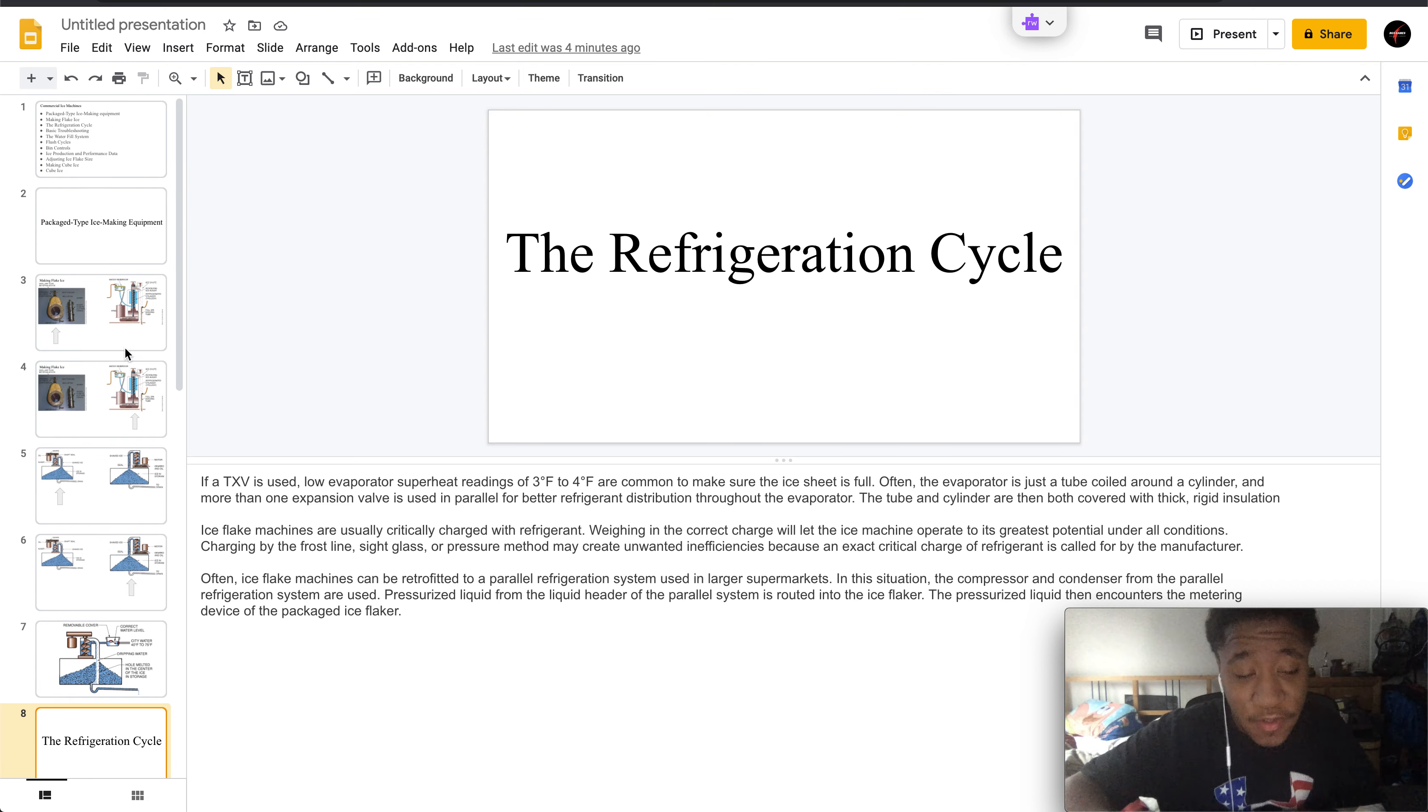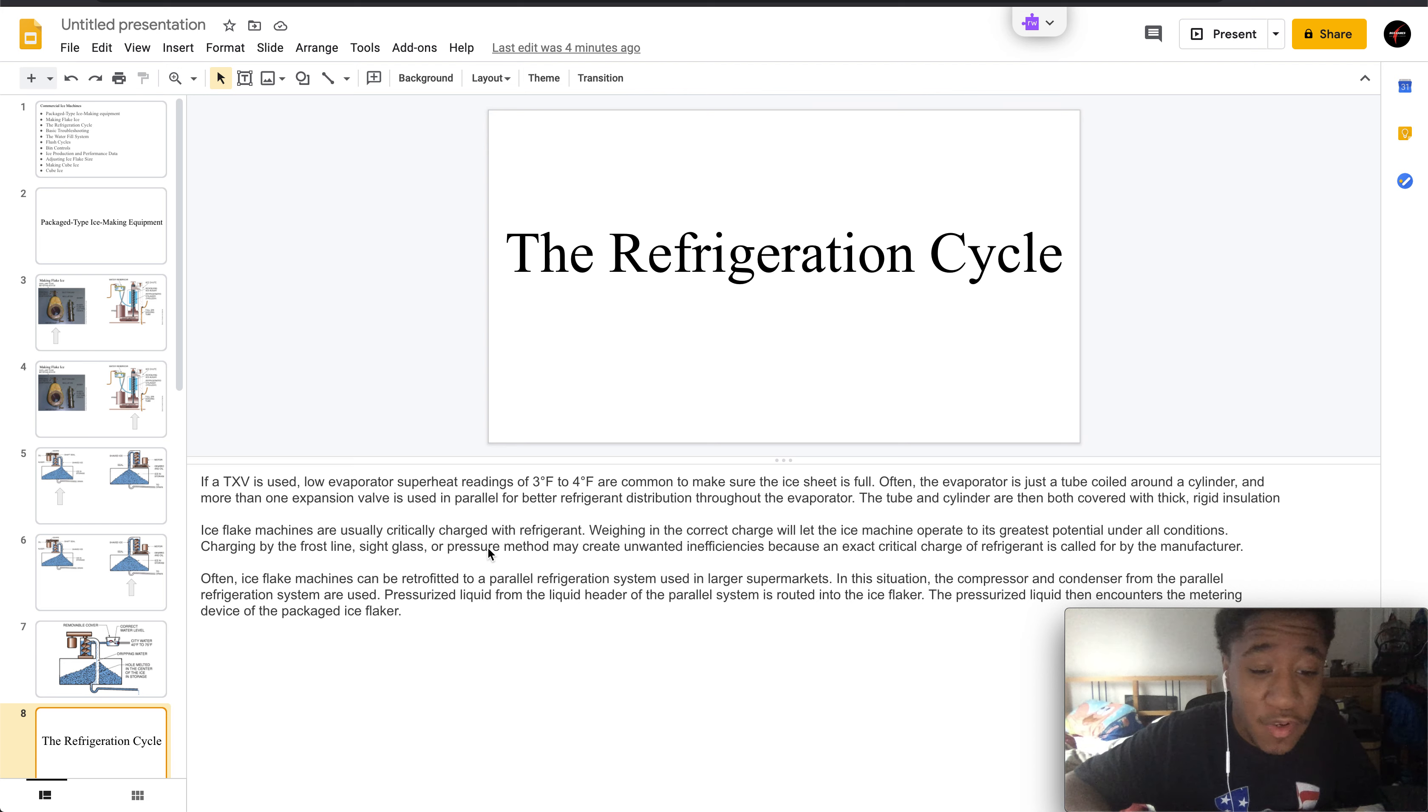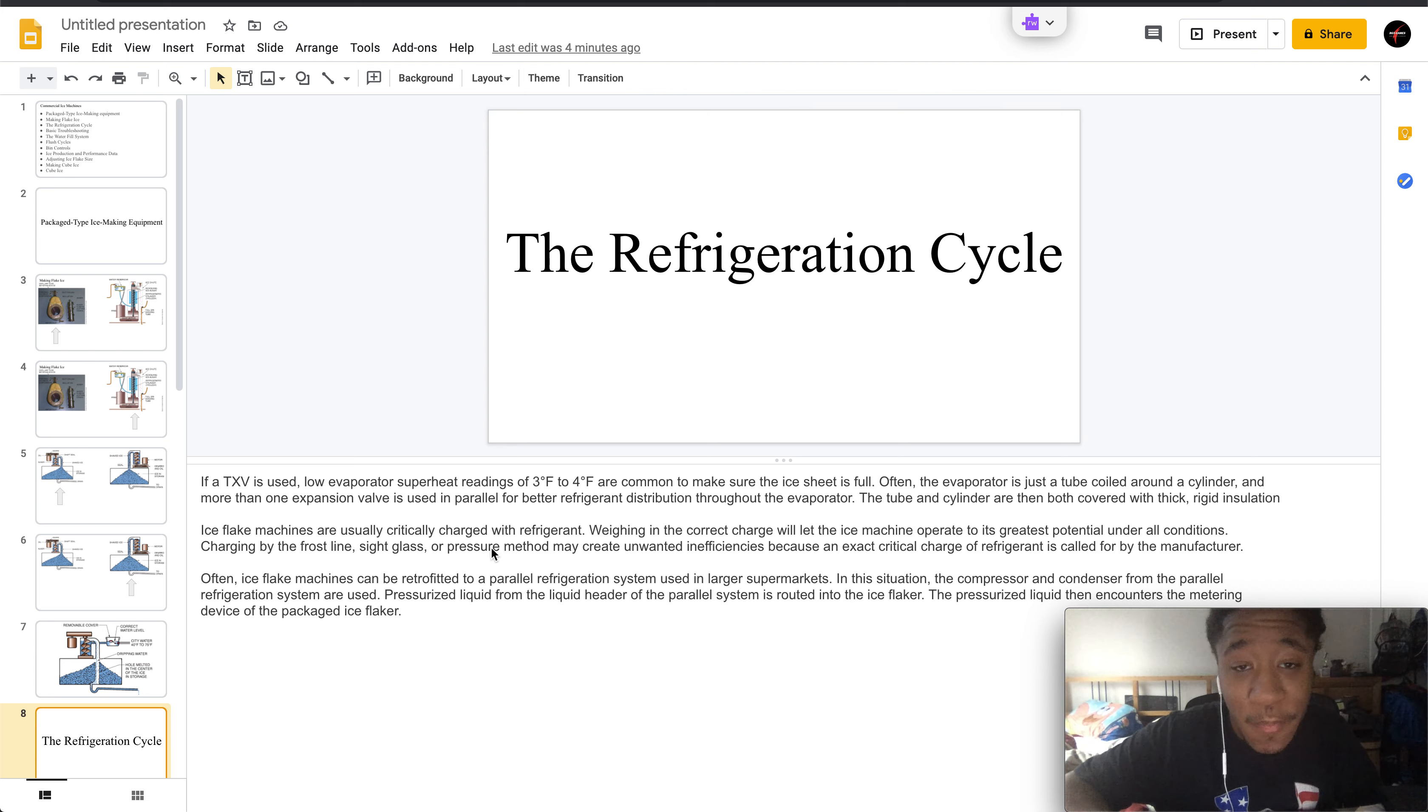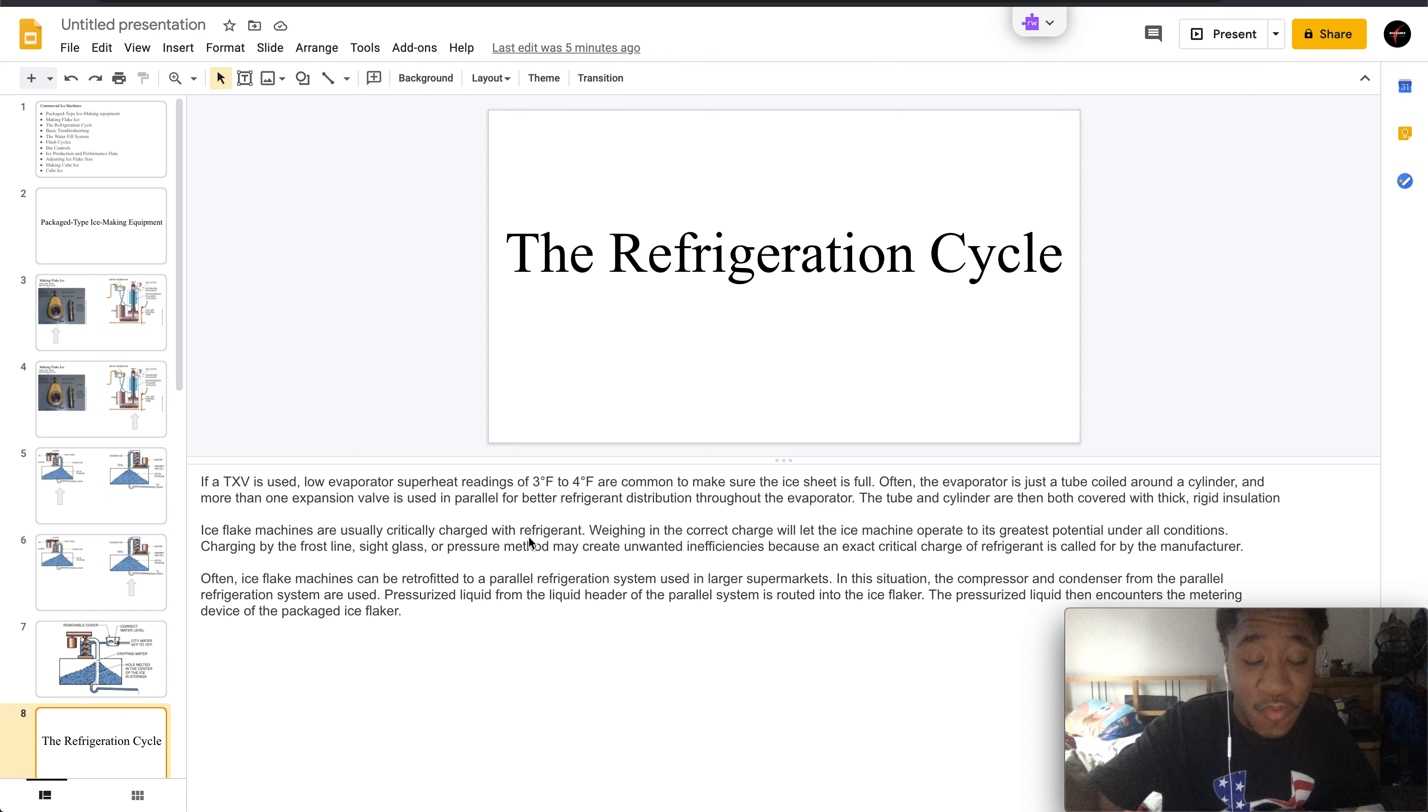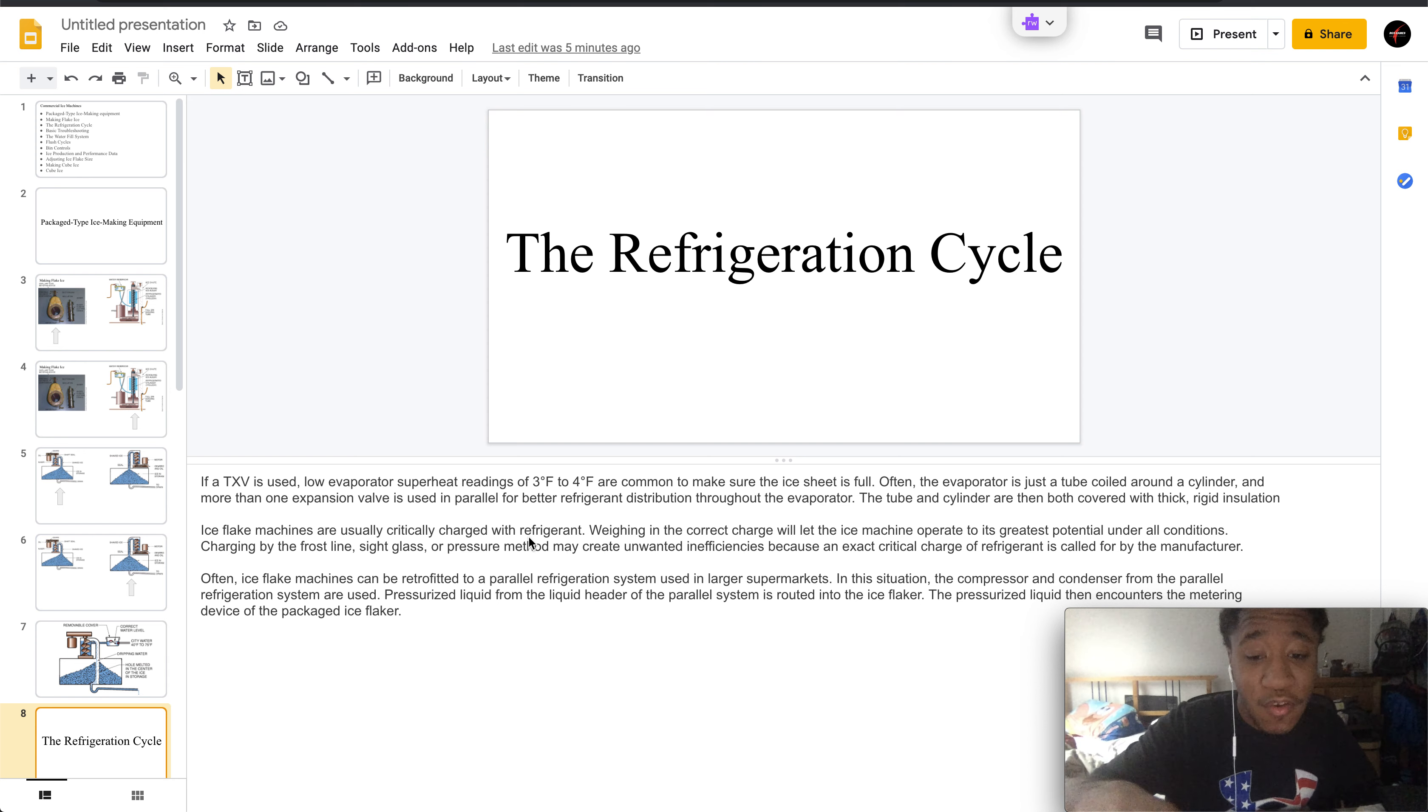If a TXV is used, low evaporator superheat readings of 3 to 4 degrees are common. This is to make sure the ice sheet is full. Often the evaporator is a tube which is coiled around the cylinder, and more than one expansion valve is needed and used in parallel for better refrigerant distribution throughout the evaporator.